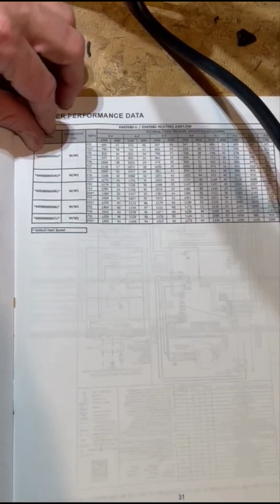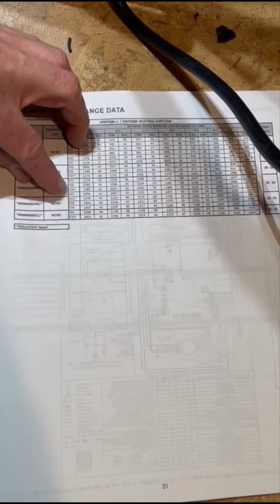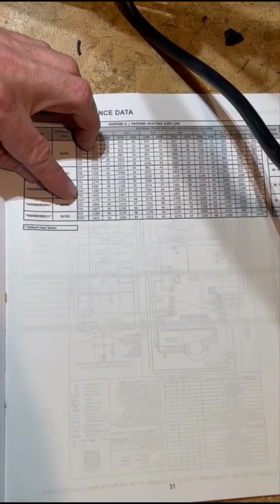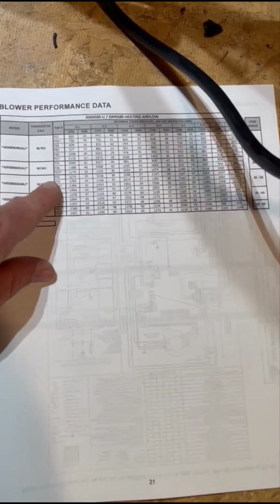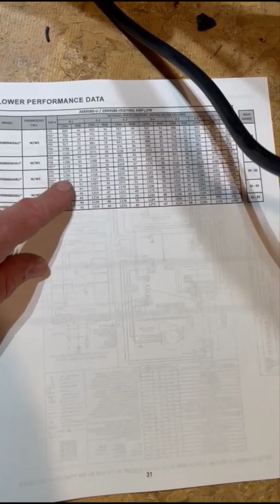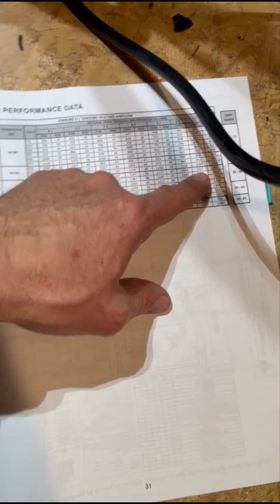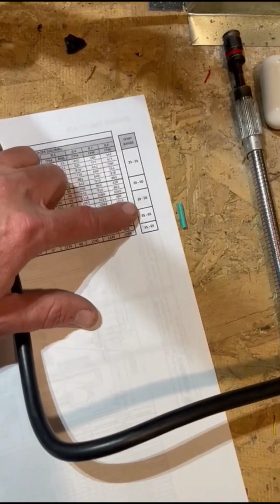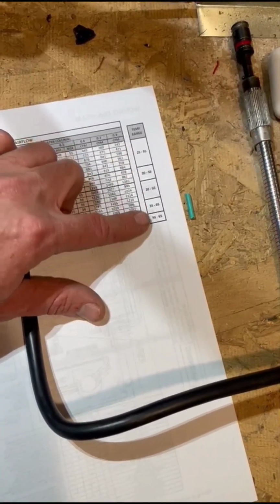Now on the second page, it's the heating chart. So you're gonna go 4-ton 60, factory default is F04. You're gonna go F04, and you're gonna go all the way to the side, and it's gonna show you the airflow, and it's gonna show you the temperature rise. So you have the temp rise on different units here. Basically the temperature difference between the supply and the return, what it needs to be so it doesn't overheat.